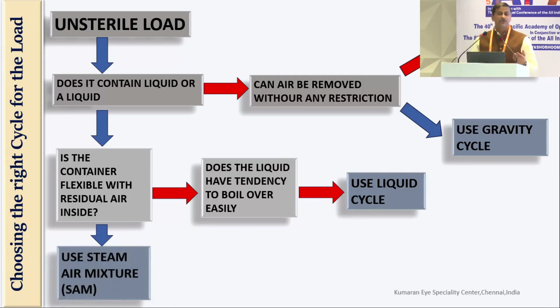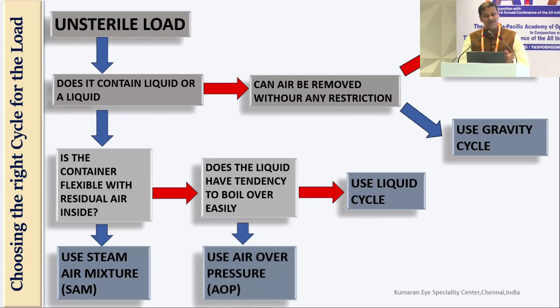So what is steam air mixture? Most of the autoclaves have the provision of letting in the normal air from the atmosphere into your autoclave, which is the cycle present in most of your autoclave programs. And if it boils over, use the air over pressure, which prevents it from doing so. See, these two protocols are just for interest's sake, and if you are going to autoclave fluids, suppose you have a multi-specialty hospital where you use a common autoclave, these are the questions you should answer. But if you're a pure standalone eye care hospital, then the top part of your chart holds good, because we don't autoclave any liquids nor your visco.